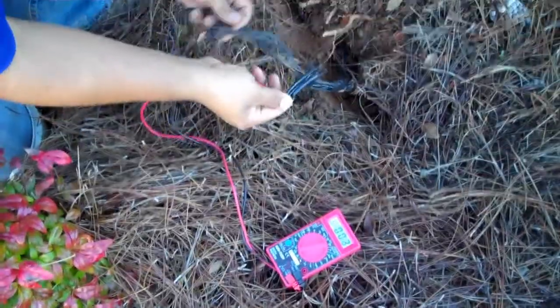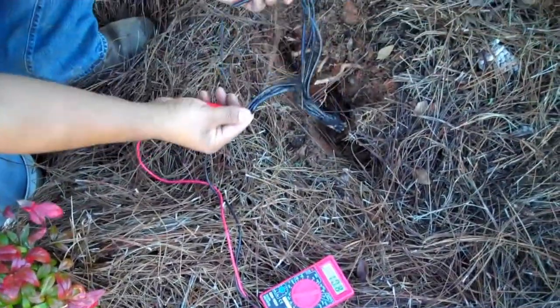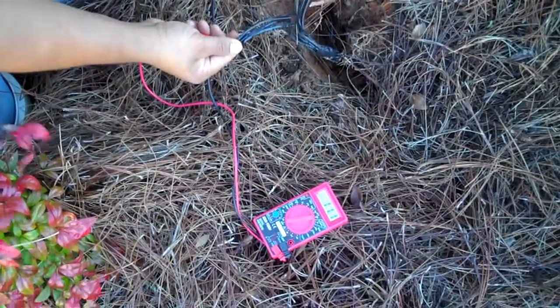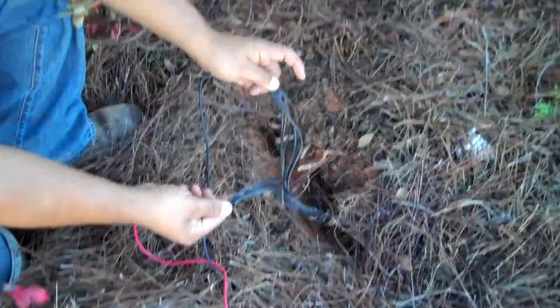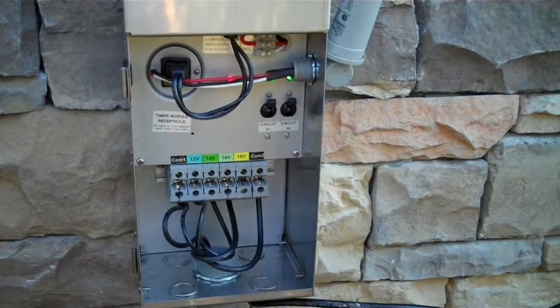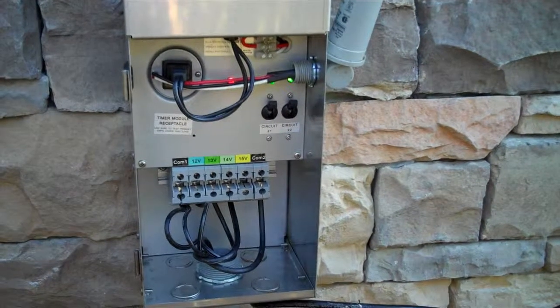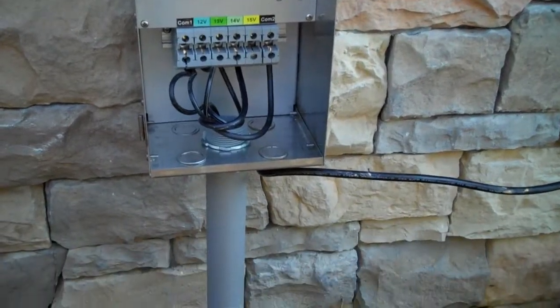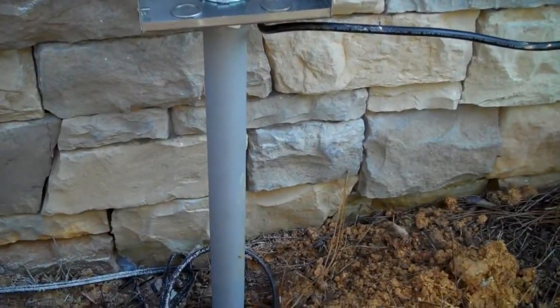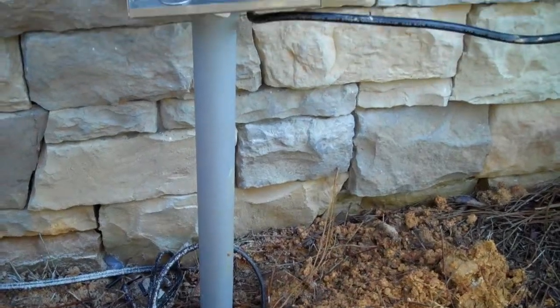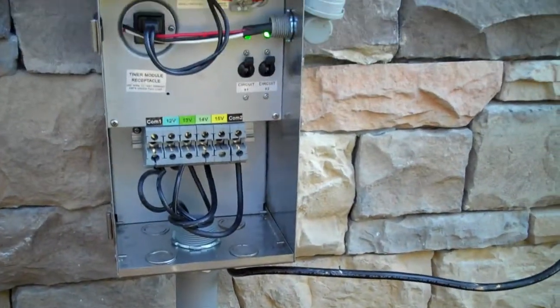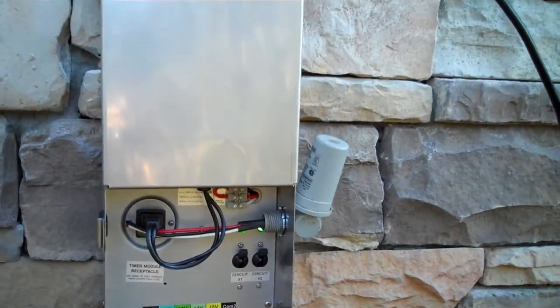Once you have connected your power wires to the desired taps, go to each hub and test the voltage to ensure that it is in the desired range of 11 to 12 volts. Use a voltage meter to test each connection point. After you have finalized your voltages at each hub, test your amp load to ensure you are below the maximum load.